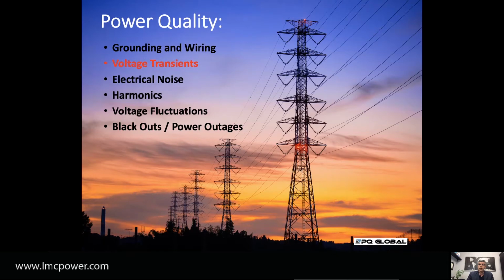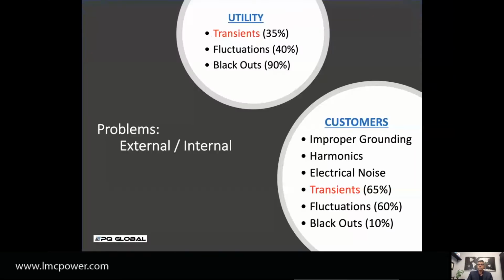So today we're going to concentrate on what's called voltage transients. And I'm going to discuss a little bit of the misconceptions that we see in the market. A lot of people, when they see transients, refer to it as lightning, something that comes from the outside. And as you can see, only 35% of the transient problems come from the utility side—either lightning, substations, transferring, other things that can come into your building and cause havoc. But as you can see, 65% of the problems with transients are not related to lightning.